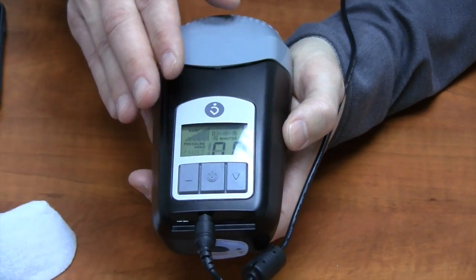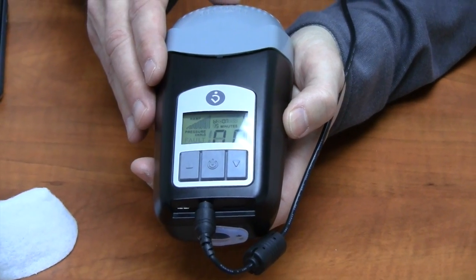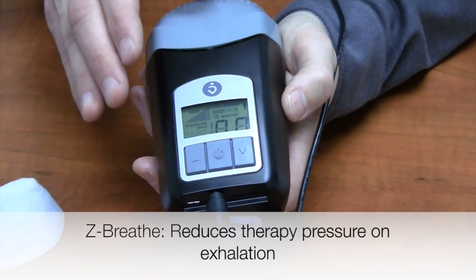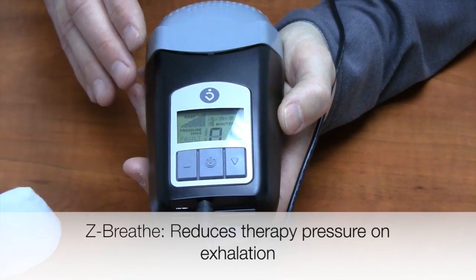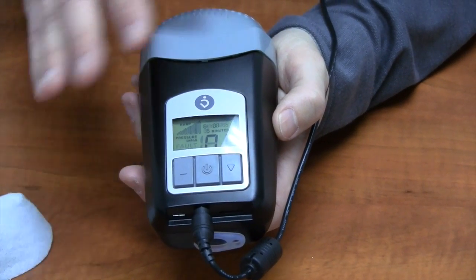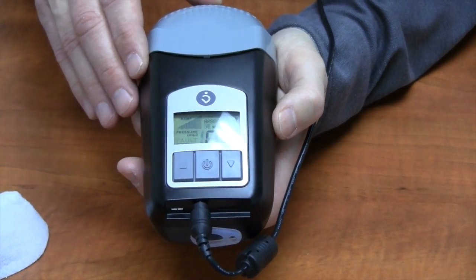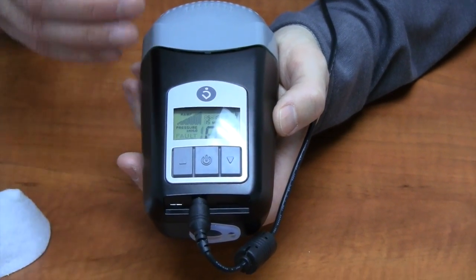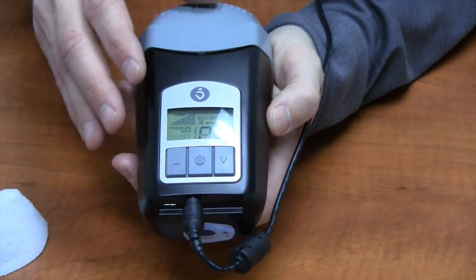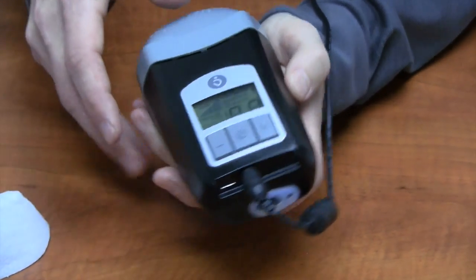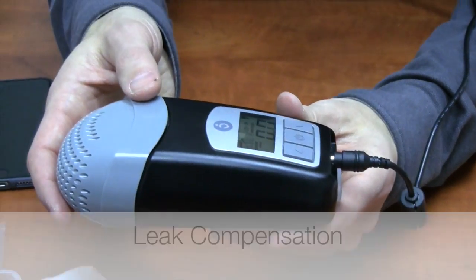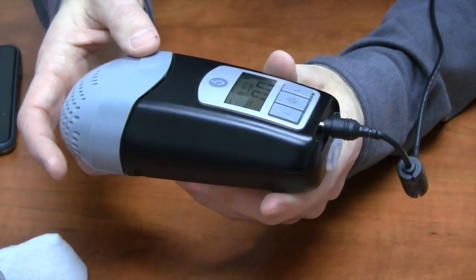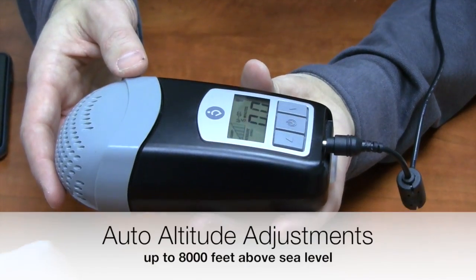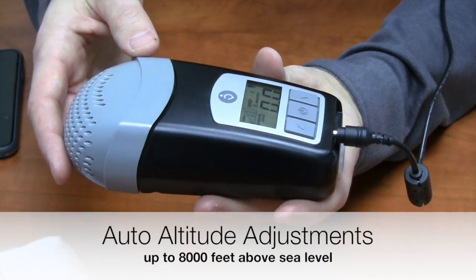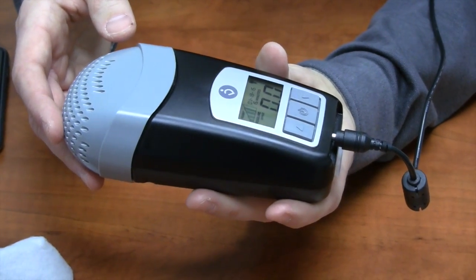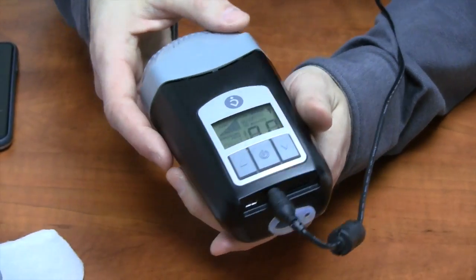Another feature that this has is called Z-Breathe. That's been enhanced and made more comfortable also. So the Z1 automatically reduces the air pressure in the mask to relieve pressure when you exhale and to level out the pressure differences in your natural breathing pattern. So basically the unit is going to reduce pressure upon exhalation, so it's trying to breathe with you, not against you. Leak compensation. The Z1 automatically compensates for minor air leakage to help ensure proper treatment is maintained. It has auto altitude adjustment up to 8,000 feet above sea level. And for air travel, the Z1 adjusts to an airplane's cabin pressure and is approved for use on all airplanes.